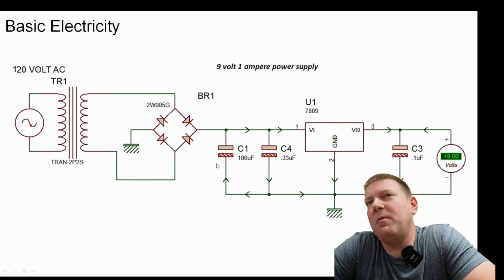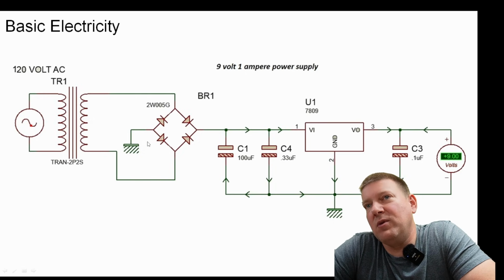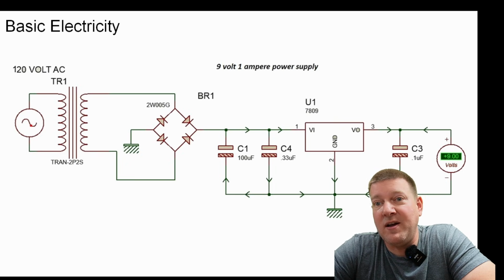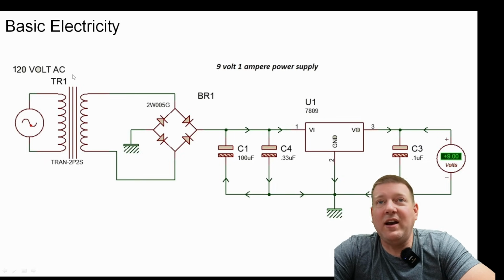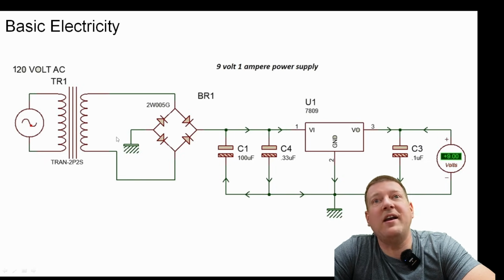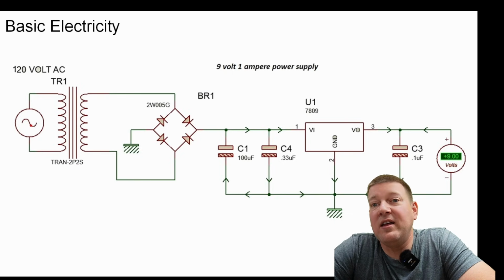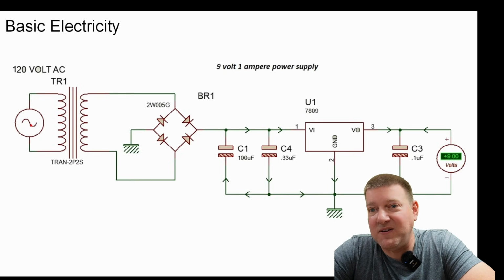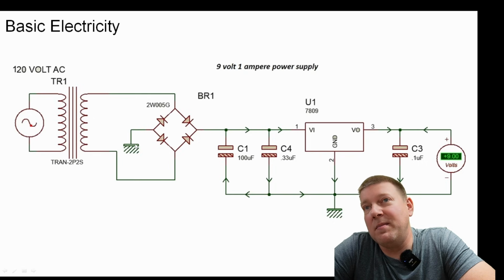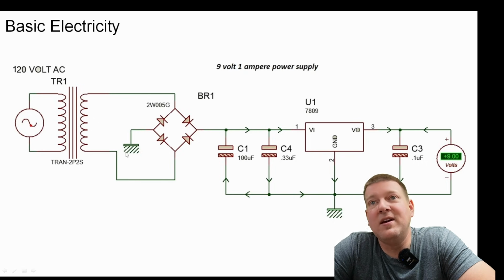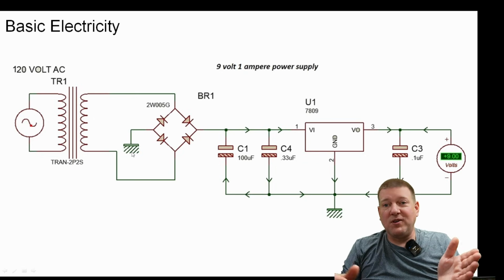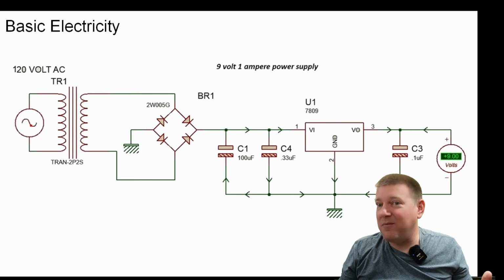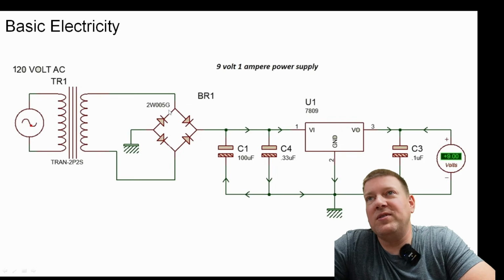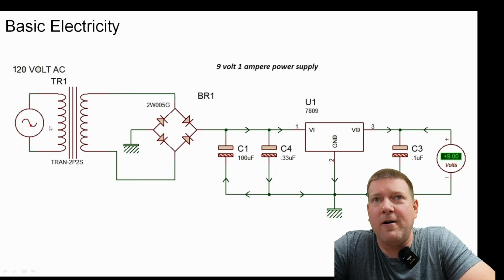And this type of power supply right here does get rid of noise, but what it does is it puts ground back into the formula, right? In a true isolated power supply, you are separating the left side from the right side, and everything after the right side doesn't touch ground again. It's not going to. That is because otherwise you are making it so that people can be shocked, because now the voltage is being referenced to ground again, which means you and I are at ground potential again. So this here is a very simple schematic of what's going on.